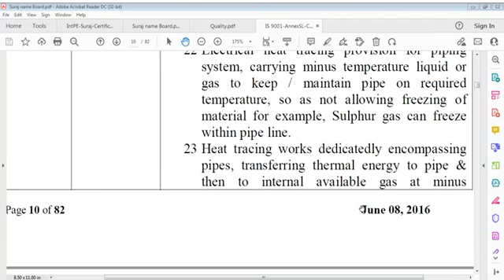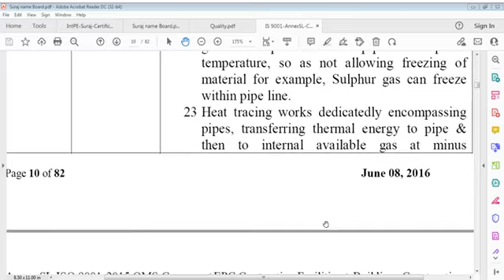Heat tracing works dedicatedly, encompassing pipes, transferring thermal energy to pipe and then to internal available gas at minus temperature, so that gas does not freeze in pipe but keeps on flowing at specified temperature and velocity.